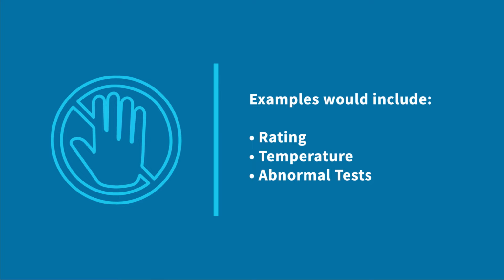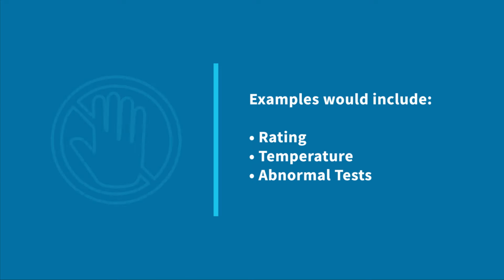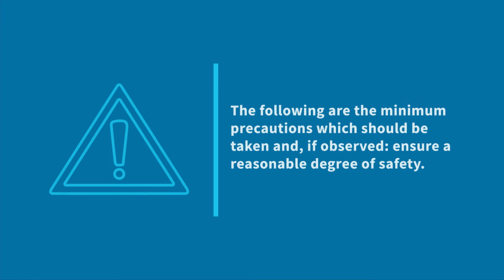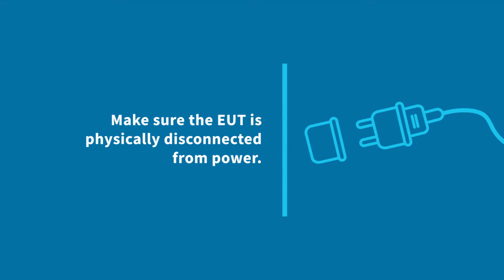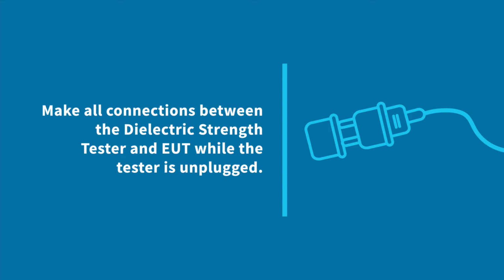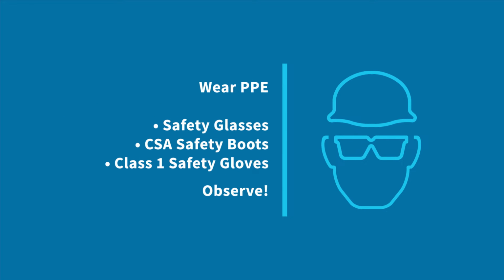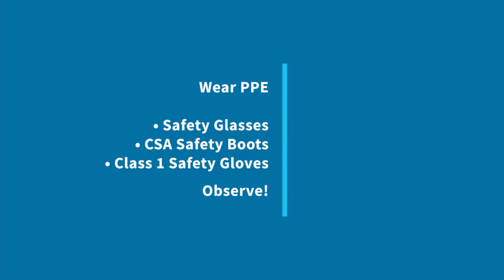The relatively high voltages used in testing the dielectric strength of insulation are dangerous to life, and the utmost care should be taken while conducting these tests. The following are the minimum precautions which should be taken and, if observed, ensure a reasonable degree of safety. Safety precautions. Make sure the EUT is physically disconnected from power. Make all connections between the dielectric strength tester and EUT while the tester is unplugged. Wear all necessary PPE including safety glasses, CSA approved safety boots, and Class 1 safety gloves.